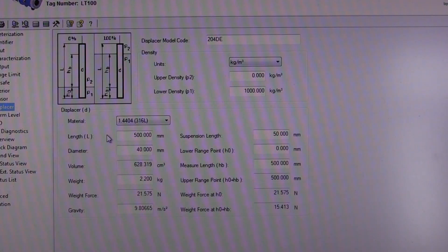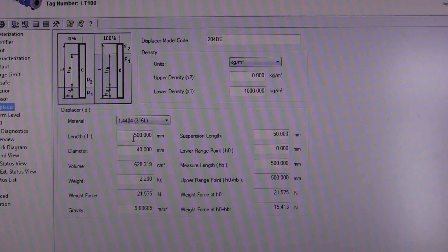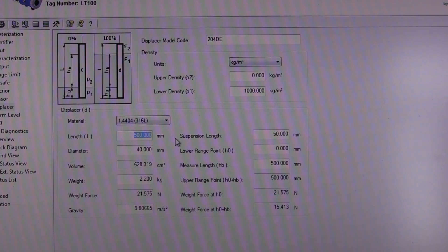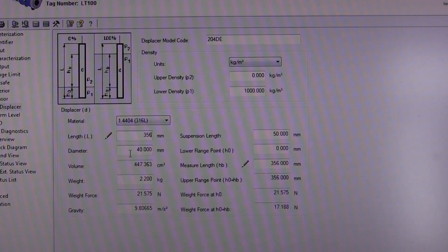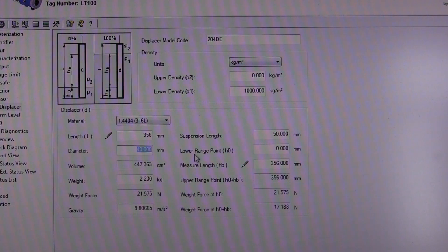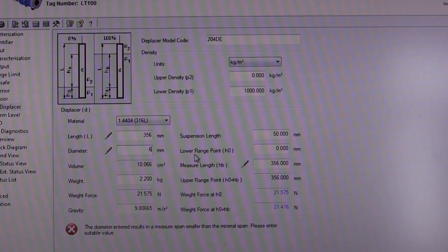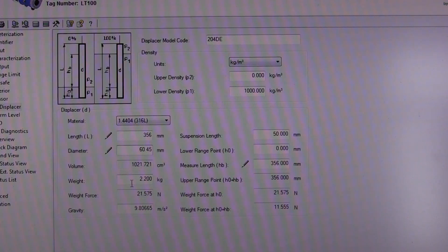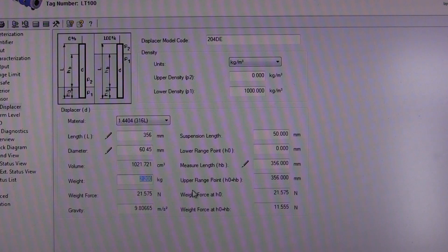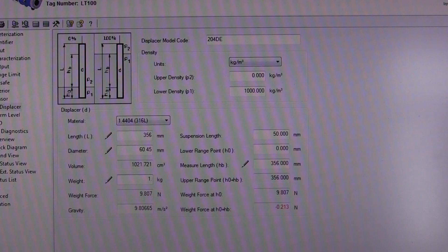First thing we do is enter our displacer length, which in this demonstration is 356 millimeters. We enter the displacer diameter, which is 60.45, and we enter the weight of the displacer, which for this specific demonstration is 1.805 kilograms.